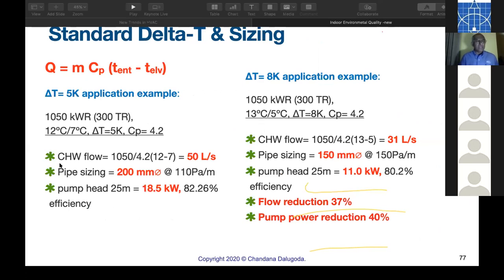I have a small example, a delta T application. Say 1050 kilowatt refrigeration load, 300 tons, operating at 12/7, delta T 5K, CP 4.2. You have a chilled water flow of 50 liters per second. Nominal pipe size would be 200 millimeter. If you select a pump with a 25 meter head, it would be 18.5 kilowatts with 82.2 efficiency.